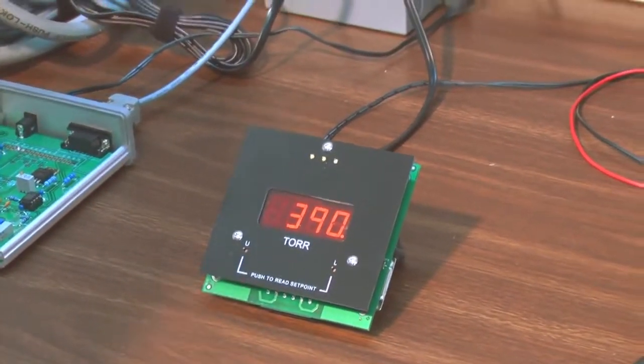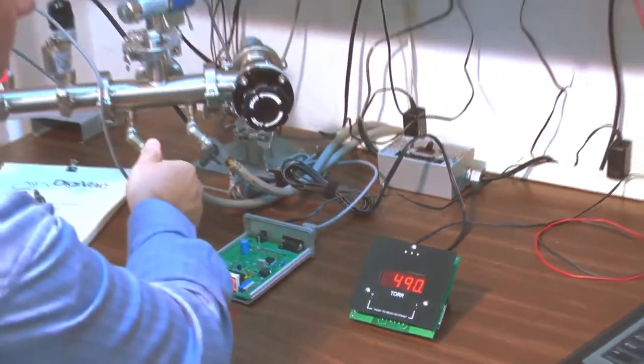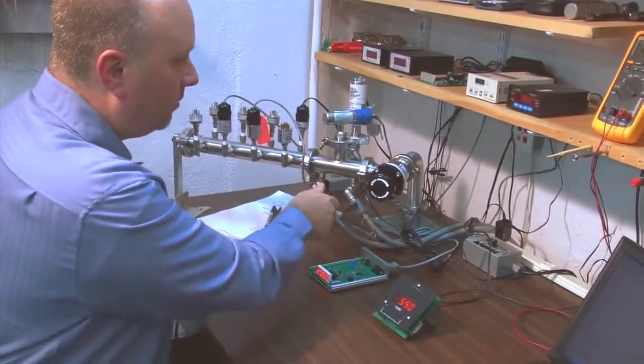440 torr, 390. Still in spec, a little on the low side. We're going to take another reading at 600 torr.